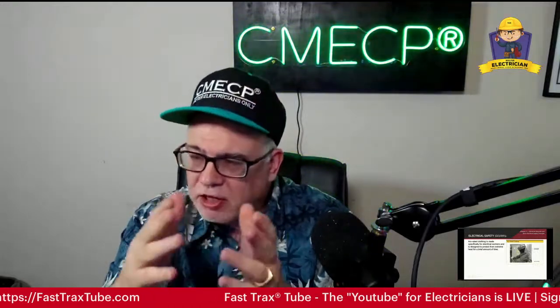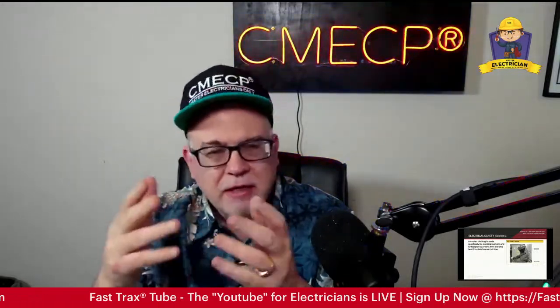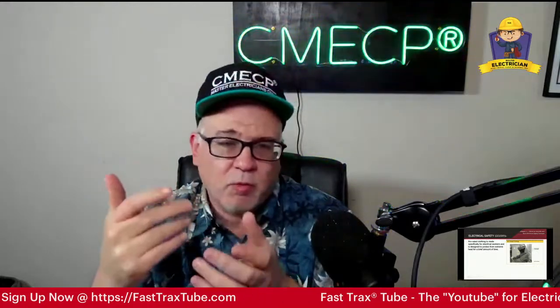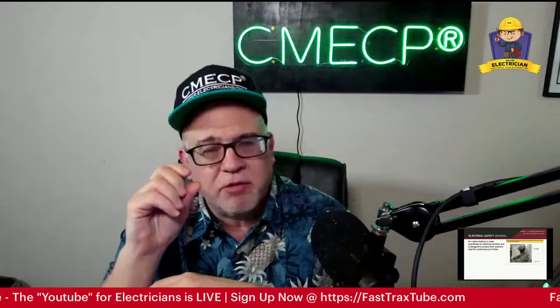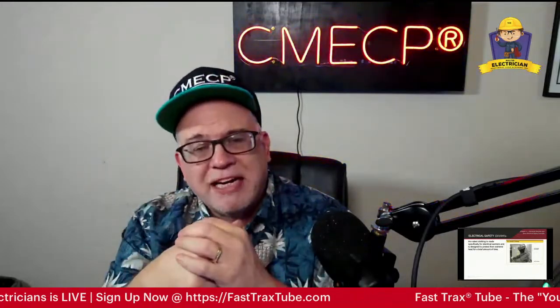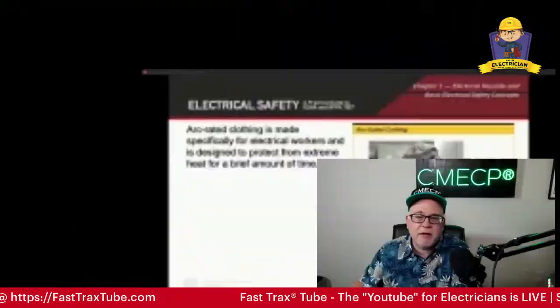But if you're an engineer who designs these systems, there are other ways to do this. NFPA 70E is probably the easiest way, and it's the way I teach, because I want electricians to know they have a document they can go to that's not overly cumbersome but gives proper guidelines. Anything not covered there, you can consult a design engineer familiar with these locations and this type of energy. But following NFPA 70E is what I recommend right from the get-go.